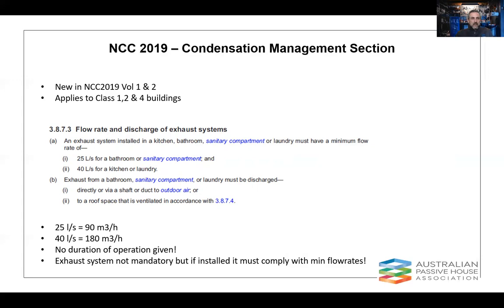Now, it is written in a slightly interesting manner in that it's basically saying if an exhaust system is installed, it must comply with these values, rather than saying you must install an exhaust point of this rate. But what we find with an MVHR system is we are going to have extract points there, but we also don't want to extract anything like the volumes they're talking about there. So for example, for bathrooms or sanitary compartments, they're talking about a minimum of 25 litres per second, which is 90 cubic metres per hour. And for laundry, it's 40 litres a second or 180. Now that's obviously well above what we want to ventilate for a typical laundry or bathroom.